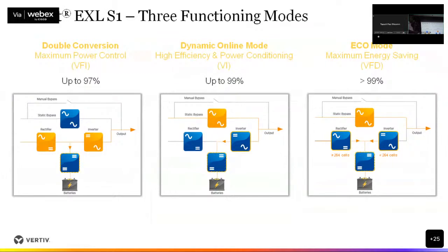But one advantage: what happens if your input utility voltage goes out of tolerance, because it is voltage independent. Here we don't correct voltage. We take care of the rest of the parameters. If voltage goes beyond a limit where you don't want it, it will automatically turn the load to double conversion. That happens automatically based on the quality of power you are getting, and it keeps monitoring the utility power and changes the mode.